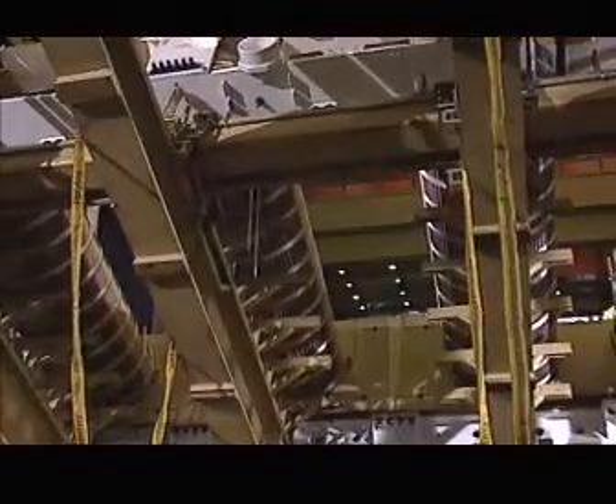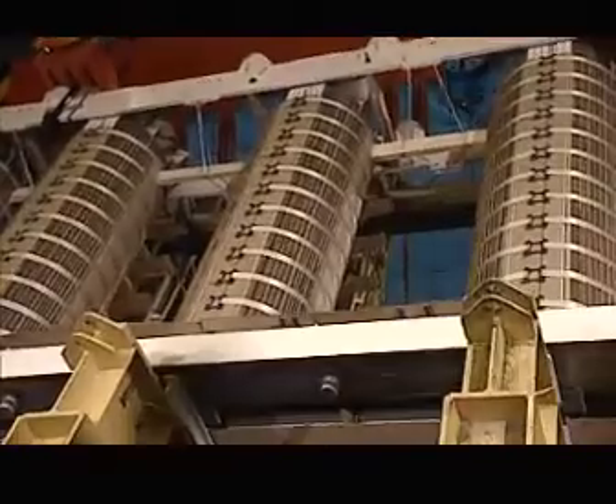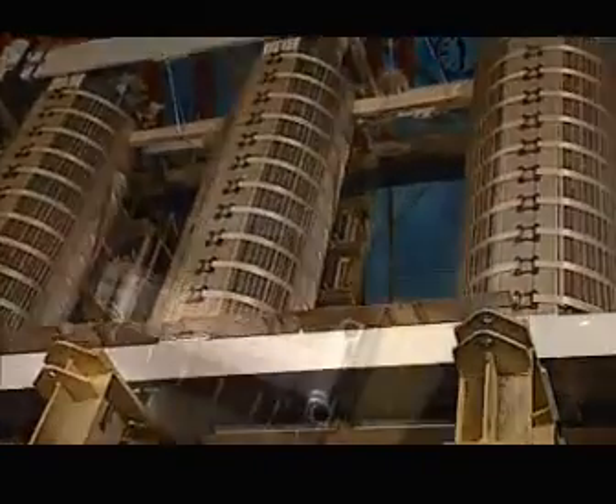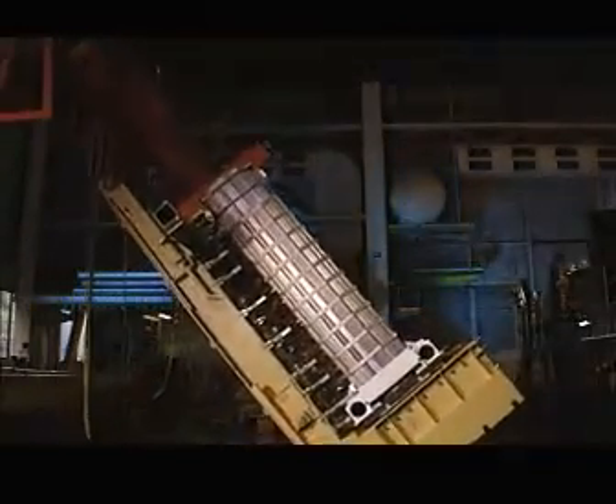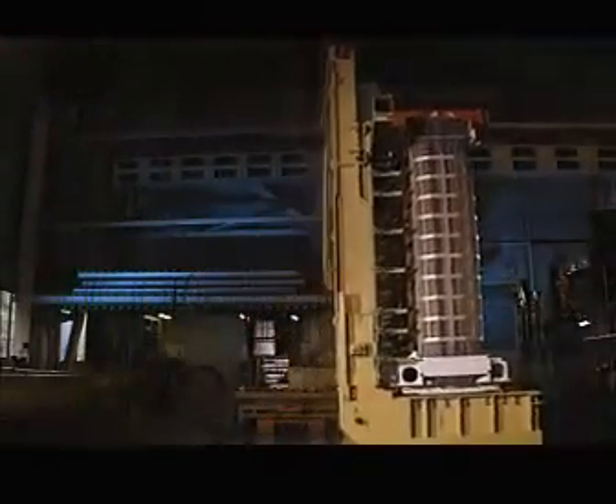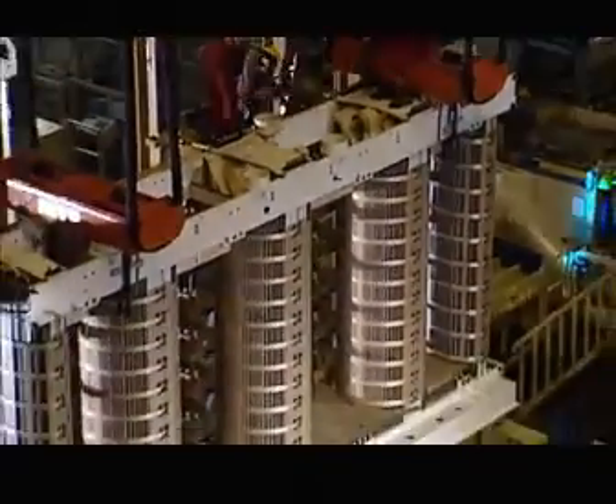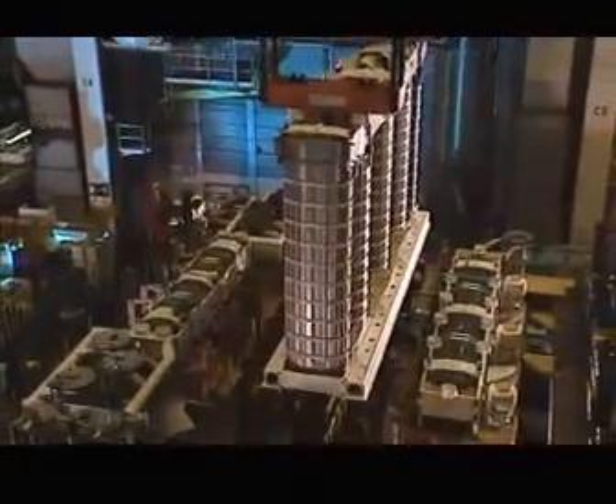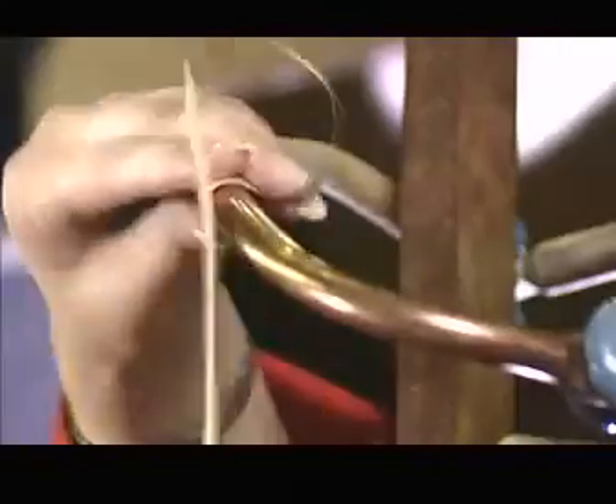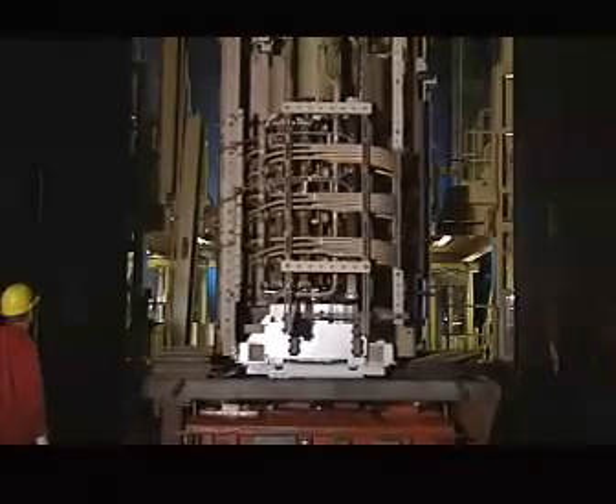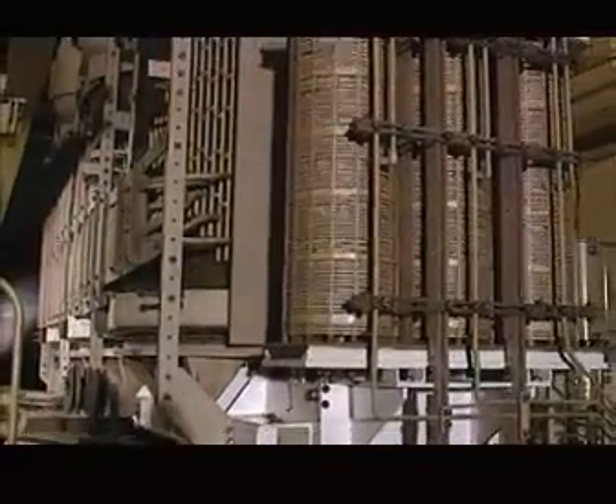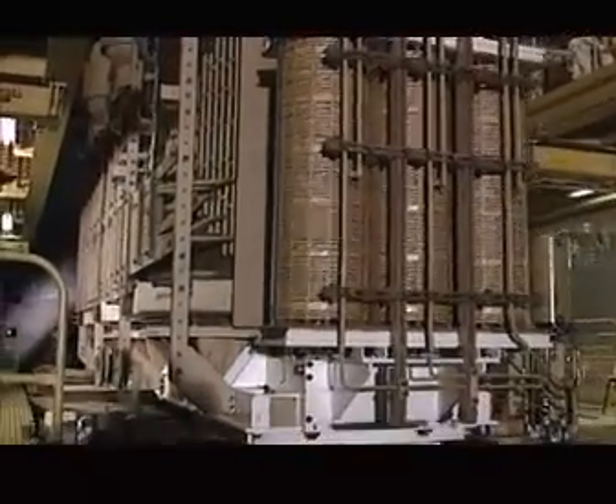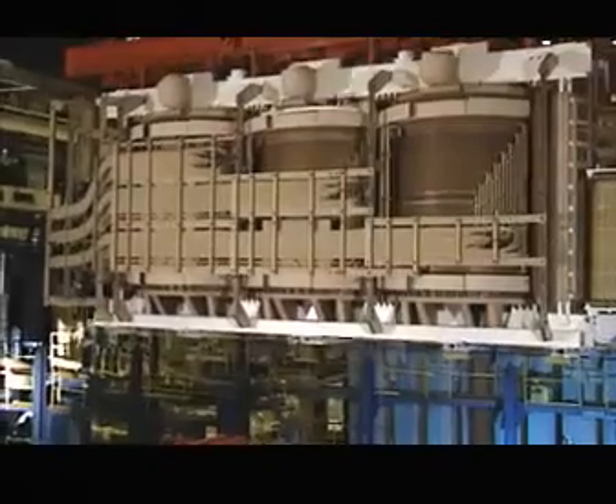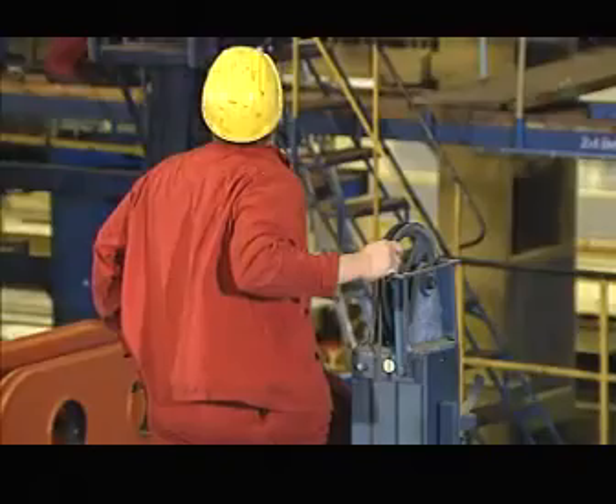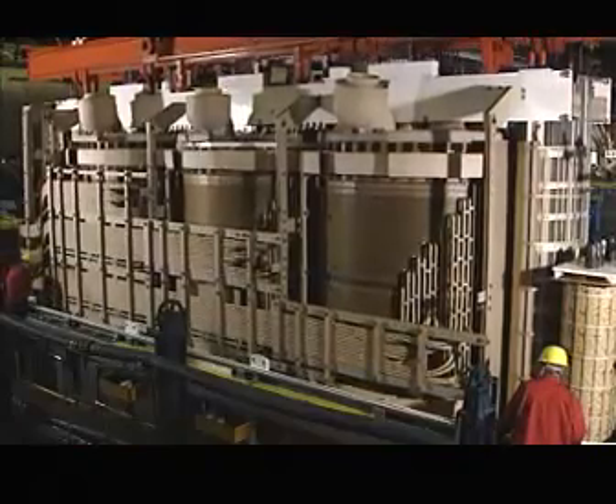This is the core of a three-phase transformer. It weighs about as much as a jumbo jet on takeoff, a good 300 tons. It's set up using giant maneuvering equipment. Then we assemble the active components, clamping devices, and on-load tap changers. When the active components are dried out using the vapor phase method, up to 1,000 liters of water can evaporate. The core and coil are inserted in the tank. Several hundred tons have to be positioned to the nearest millimeter.